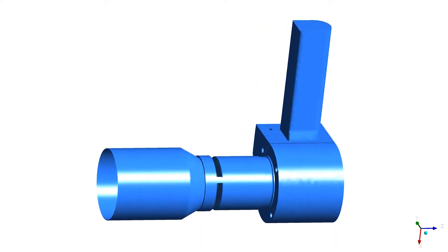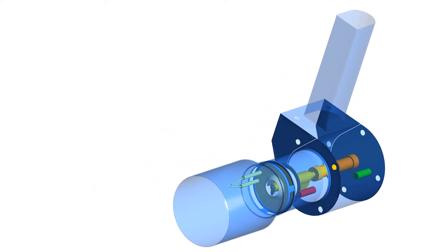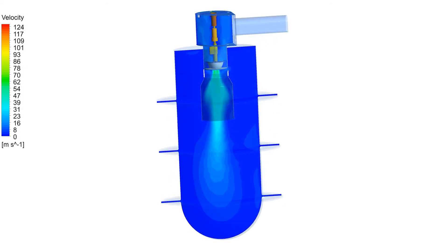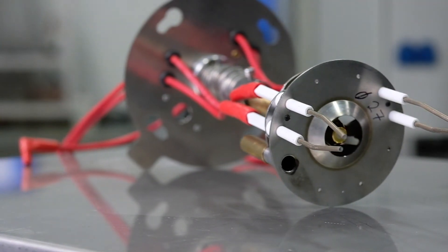The next step was to develop a reaction mechanism to predict the combustion process of pyrolysis oil. These two models are combined in a CFD application, and we are now capable of predicting the flame pattern and temperature distribution in a boiler in a very complex geometry, using new fluid properties that we didn't have before the project started.